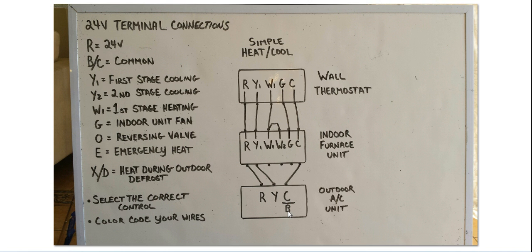I've put C and B. This B, when I put for common, it only relates to the outdoor unit, not to the indoor thermostat. Because depending on what model, I know Trane used to use B as your common in the outdoor unit. So just to throw you a bit of a curveball. So that's why I've mentioned it there. But this B isn't for the indoor thermostat ever because B is similar to your O.